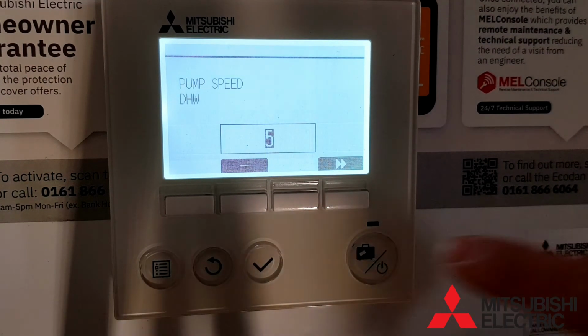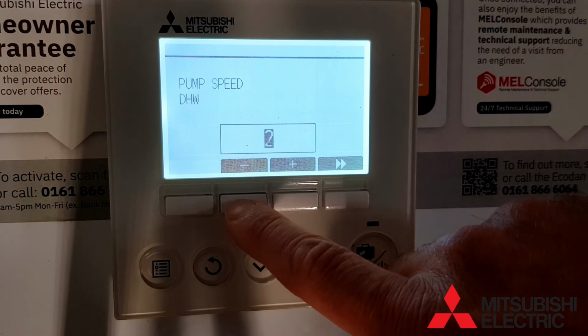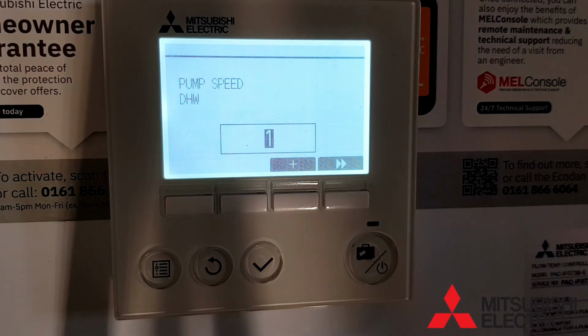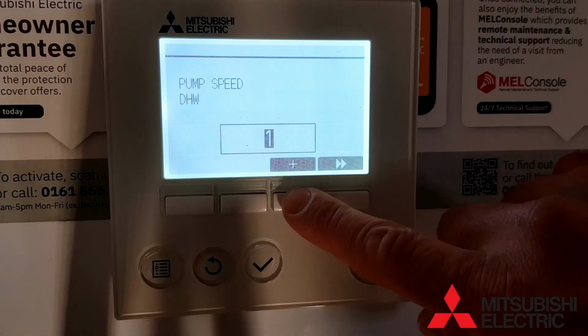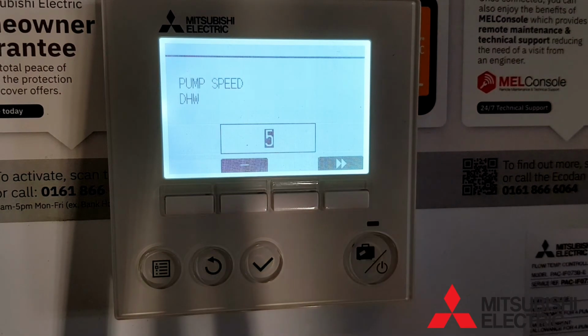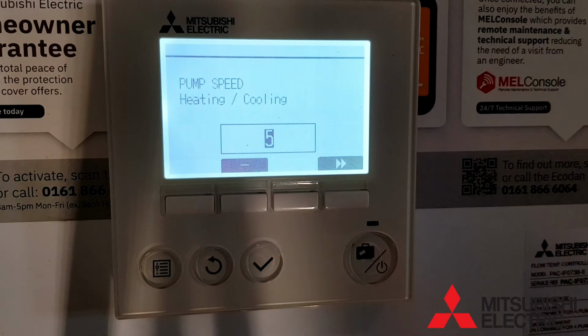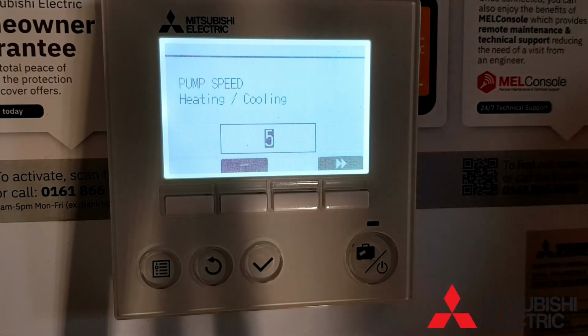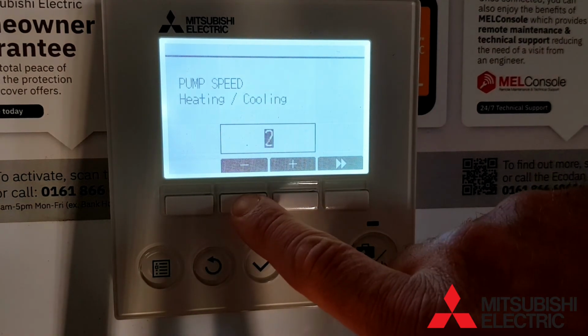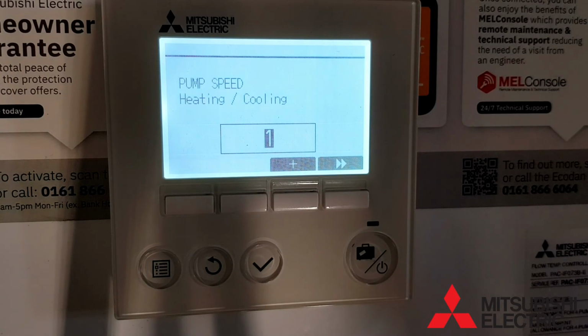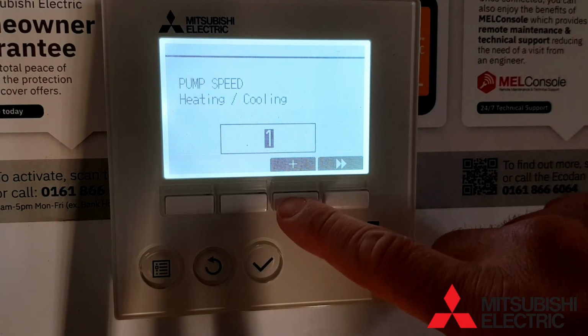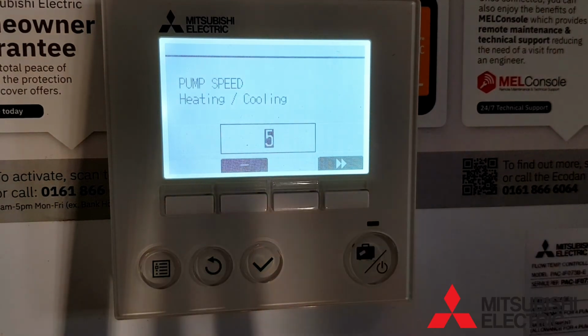Now we can set the domestic hot water pump speed. So this is the speed it's going to circulate the water through your plate heat exchanger in hot water mode. You now need to do the same for the heating pump. You can adjust it up and down from speed 1 to speed 5. Obviously speed 5 is your highest speed, will give you the most flow.